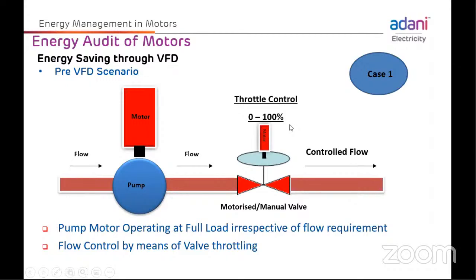So that throttling loss can be removed by putting a VFD for this motor. That is a simple scheme. Once you put the VFD, you can open the valve 100%, and this flow is controlled by the VFD by changing the speed of the motor.